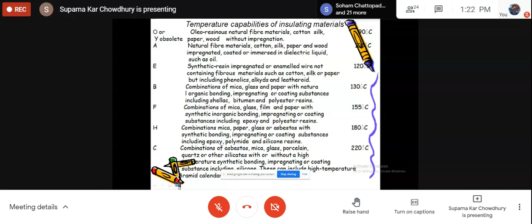So this insulation is very important, and as I've told, when we go for higher insulation temperature grade, then the mechanical properties deteriorate. And the insulations, when subjected to higher temperature, deteriorate. Another thing which affects insulation is vibration. Particularly for the rotating part, the rotor windings, that insulation is a problem because it is always subjected to vibration. The same insulation which can insulate the static stator winding to a high temperature can withstand only a lower temperature for the rotor winding. So all this has to be considered during design.